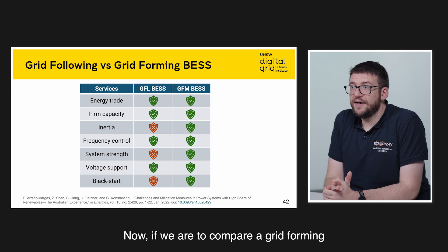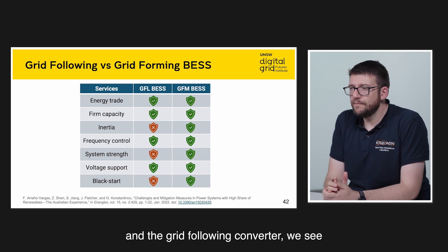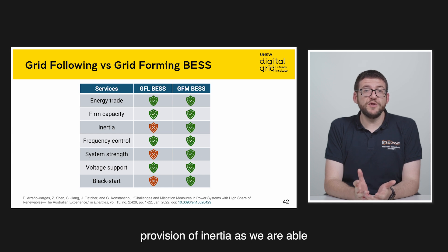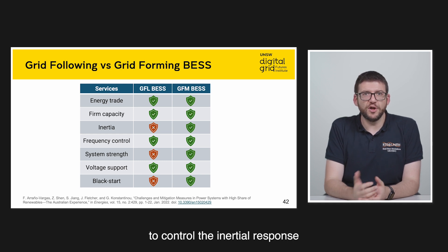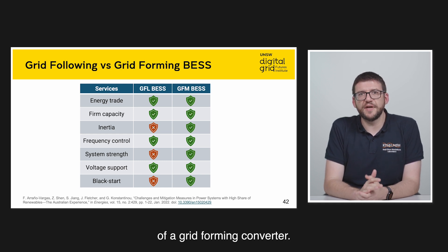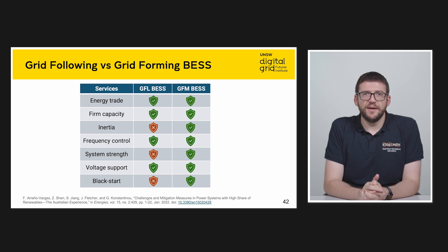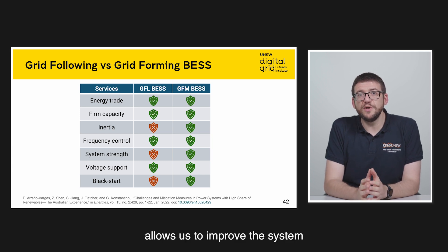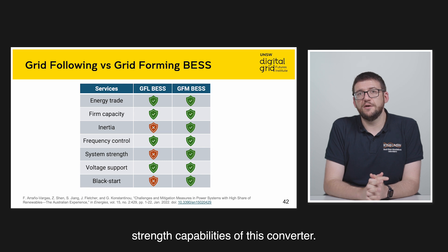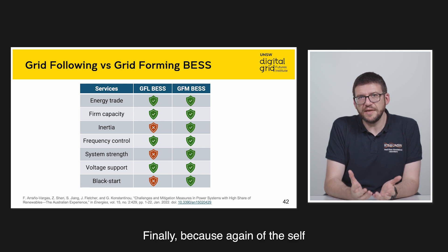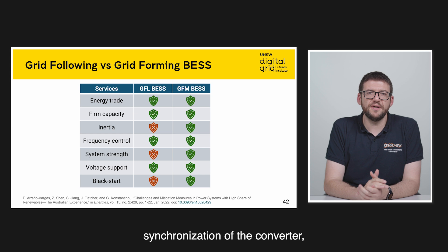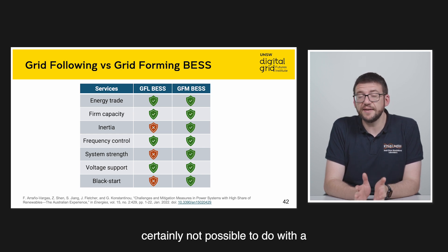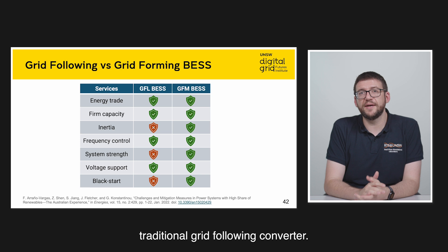If we are to compare a grid-forming and a grid-following converter, we see fundamental differences in three aspects. Firstly, with the provision of inertia, we are able to control the inertial response of a grid-forming converter. The fact that the converter also synchronizes to its own reference allows us to improve the system strength capabilities of this converter. Finally, because of the self-synchronization of the converter, we are able to offer black start capabilities, something that is certainly not possible to do with a traditional grid-following converter.